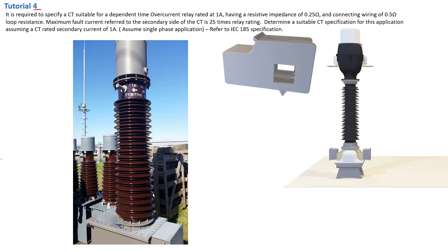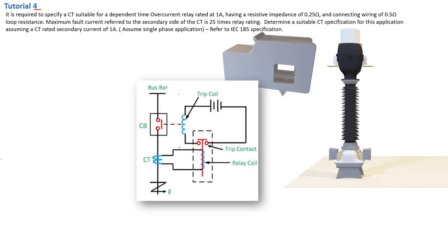Now, what is an overcurrent relay? As we can see here, the overcurrent relay rated at 1 amp is the relay connected at the secondary of the CT. This is our current transformer that we need to specify. We're not going to specify the relay — the relay is already there — but we need to choose and specify a current transformer that will work with the relay.